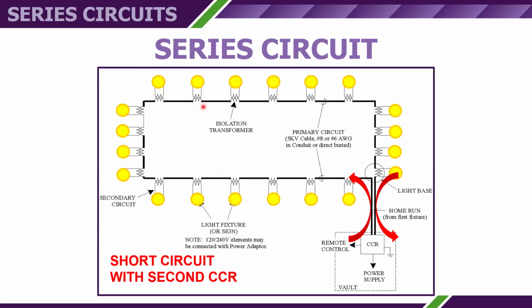Always check for current flow before opening connectors. Even if you've locked it all out and you've demonstrated that you've got an electrically safe work condition, don't break that connector in the field until you've checked it to ensure you do not have current flow. Advisory Circular 150/5340-26C, which is the maintenance advisory circular, will provide additional guidance and help troubleshooting a series circuit.